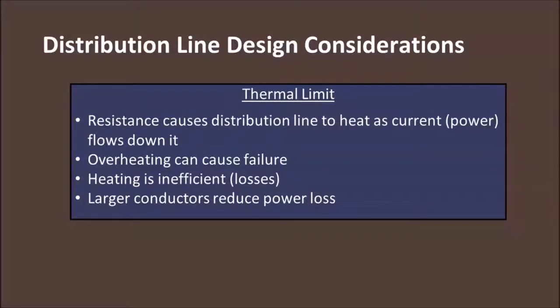We also have losses along that line. As power flows down the line, it encounters resistance and heat is generated, and that heat can be so much that the line mechanically fails or starts to sag. These losses also increase with the length of the line, so again, to counteract these effects, we would use larger conductors, which reduce the resistance and therefore reduce the losses along the line.